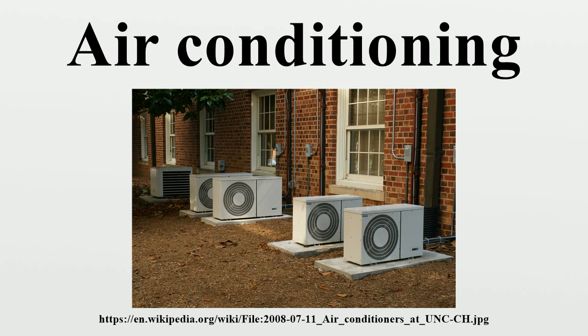Heat pump unit. A heat pump is an air conditioner in which the refrigeration cycle can be reversed, producing heating instead of cooling in the indoor environment. They are also commonly referred to as a reverse cycle air conditioner. The heat pump is significantly more energy efficient than electric resistance heating. Some homeowners elect to have a heat pump system installed as a feature of a central air conditioner.